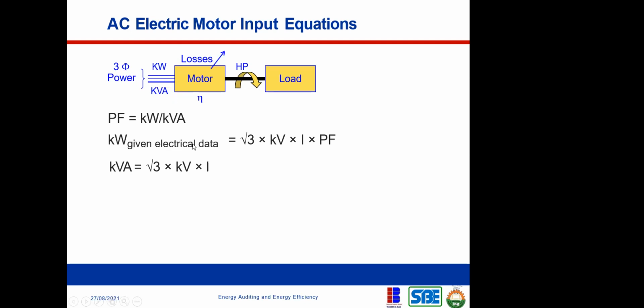The input energy is kilowatt electrical, and it is given by this equation: square root of 3 times kilovolts, or voltage, but in this case I've added K so it's now kilovolt, times amperage, times power factor. If I take away this power factor, it becomes kVA, but because we have power factor, it is now kilowatt. This is kilowatt electrical, and this is what is coming into the motor, the input energy. Like I said before, if you remove this, it becomes kVA. I also illustrated that here.